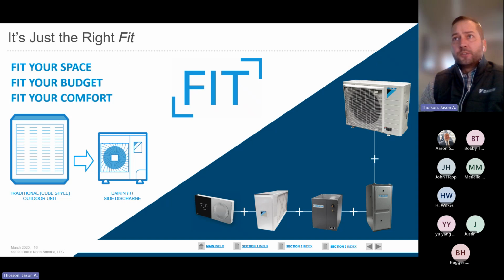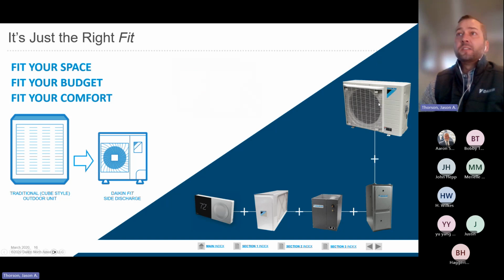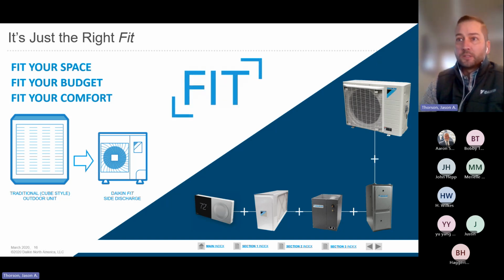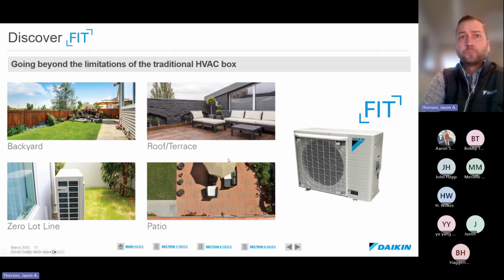So when we talk about side-discharge, this is a flagship model for Daikin called Daikin Fit. Most people see this and say, 'Oh yeah, mini splits—I've seen them all over, traveled abroad or in the U.S.' But this is actually a very traditional AC unit hooked up to a multi-position air handler, a coil, could be a gas furnace—I'll show the applications in a minute—with your filter box and controls system.